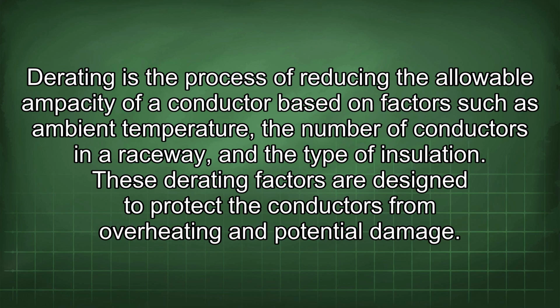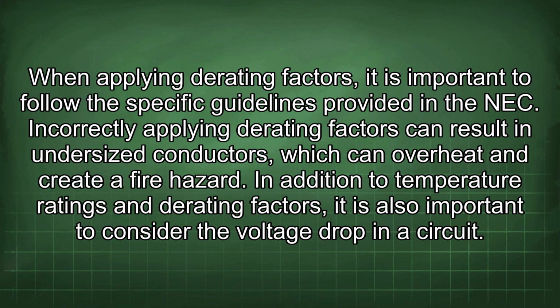These derating factors are designed to protect the conductors from overheating and potential damage. When applying derating factors, it is important to follow the specific guidelines provided in the NEC. Incorrectly applying derating factors can result in undersized conductors, which can overheat and create a fire hazard.